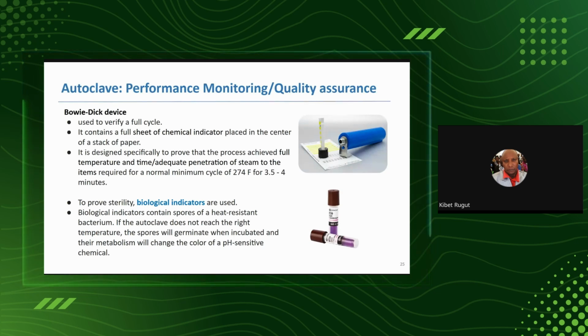Another one for us engineers is to verify a full cycle. We call it the Bowie and Dick device. You place it at the center of the stack of paper. It is supposed to prove that the process has achieved full temperature, time and adequate penetration. So you run the cycle at 274 degrees Fahrenheit for 3.5 to 4 minutes. To prove sterility, the biological indicators are used, and this one we have mentioned several times.